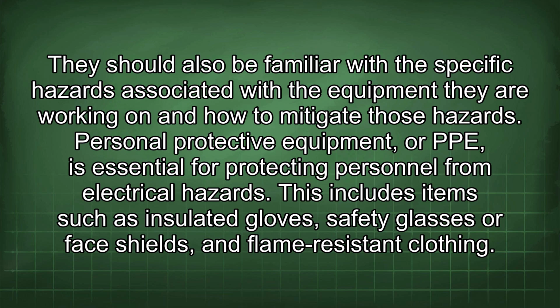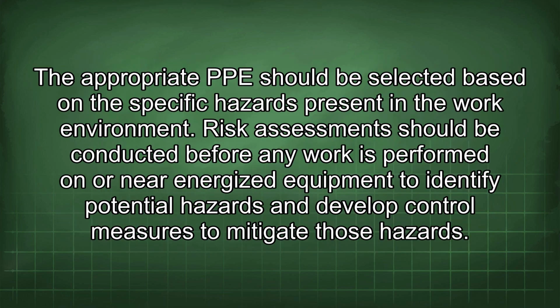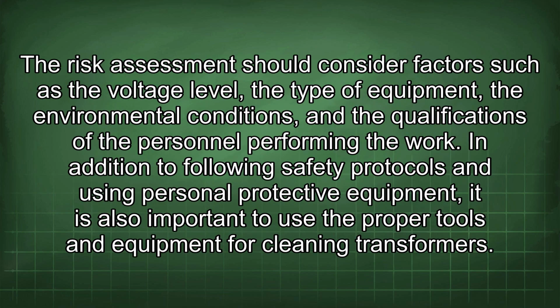mitigate those hazards. Personal protective equipment, or PPE, is essential for protecting personnel from electrical hazards. This includes items such as insulated gloves, safety glasses or face shields, and flame-resistant clothing. The appropriate PPE should be selected based on the specific hazards present in the work environment. Risk assessment should be conducted before any work is performed on or near energized equipment to identify potential hazards and develop control measures to mitigate those hazards. The risk assessment should consider factors such as the voltage level, the type of equipment, the environmental conditions, and the qualifications of the personnel performing the work.